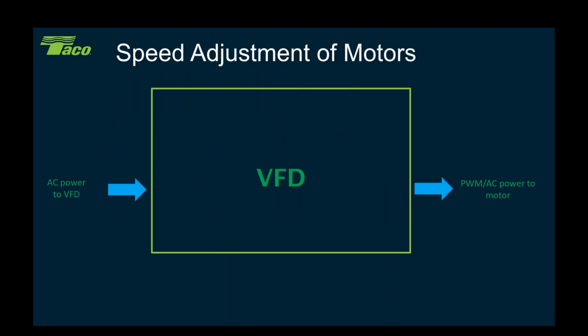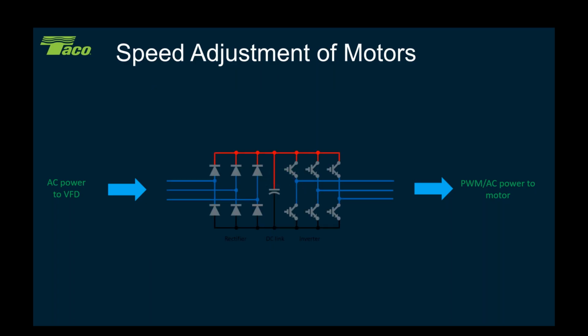So in any motor, when we're going to change its speed, unless we have a multi-speed motor, we're going to use a variable frequency drive to change that speed, okay? In that variable speed drive, we have the rectifier circuit, a DC bridge, and an inverter circuit. The rectifier circuit is on the far left-hand side, and this one is a 6-pulse drive. So I've got 6 rectifiers in there, 2 for each phase, okay? 3 of them are on the top half of the phase, 3 of them are on the bottom half of the phase, okay? Then we've got a DC bridge, and the DC bridge is what couples everything together. Then we have the inverter section. We go from AC power through the rectifiers into DC power, across the DC bridge, into the inverter, and the inverter takes that DC power and turns it back into AC power and sends it out to the motor, okay?